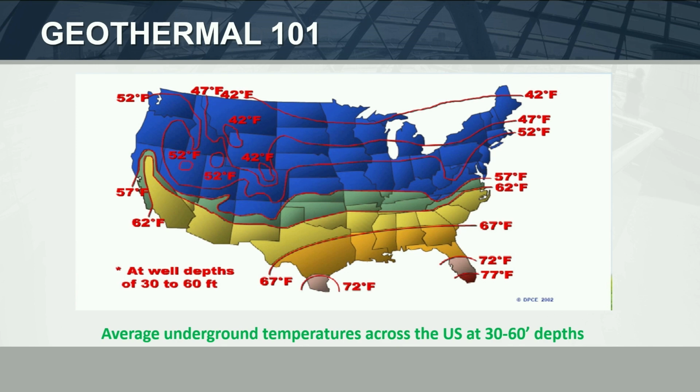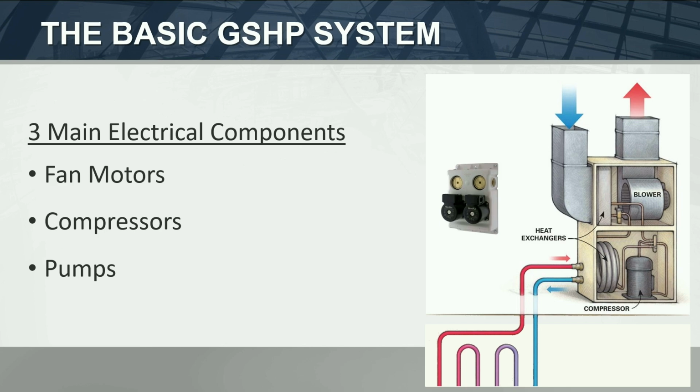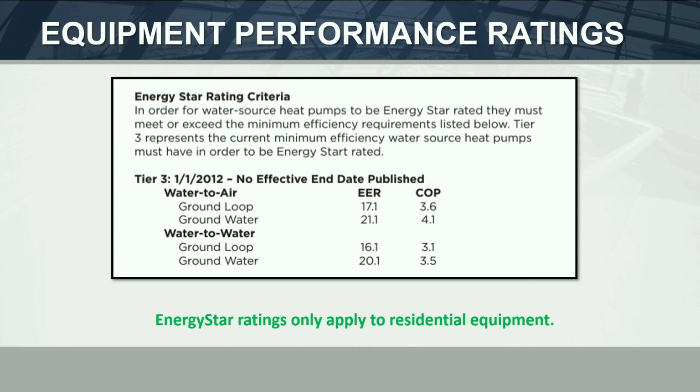Maybe you can explain the highest levels of temperature return and the lowest in the winter to the bore, which would help. Sure. So typically, like we showed before, in a closed loop system, worst case, we're looking at 32-degree entering water coming to your equipment. So typically, we're taking 6 to 8 degrees out of that loop. And then we're sending it back through the ground to recollect that energy, bring it back to your heat pump. So worst case conditions in the winter depend on what you design for. Some people design for 32. I believe the IGSHPA standard is now 25 degrees. You can have a worst case condition of 25. And then for your cooling season, residential systems, your ground loop coming in could be as high as 80 degrees in this area. Right, so your lift would be better than an air source, and that's why these are more efficient. Exactly.